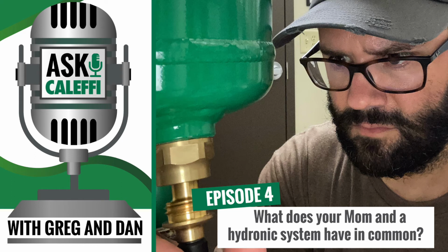Right. And then the mesh in these, so when we're talking our smaller brass ones, those are glass reinforced nylon. And then when we step to the commercial steel units, those have the stainless steel. Yeah, they do. And those will have a larger ball valve on the bottom for cleaning. So, we do have a discharge port on the bottom of all of our separators for cleaning. That's something that when you're out doing, you'll typically shut a pump off to drop the pressure in the system and then do a downward flush. Sure. Right after you remove the magnet.